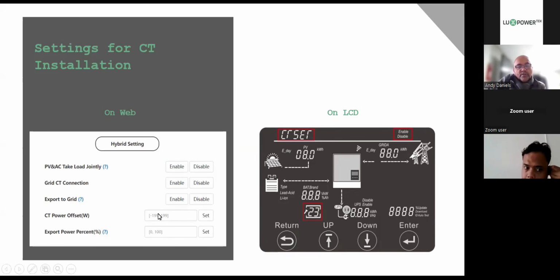So in other words, if your CT is pushing out power at maybe 50 watts, and you've set it at 0, then you can set a negative value here. You'll go negative 60 and set. It simply means that when you're generating PV power, it will always retain or pull in 60 watts from the grid to make sure that the CT doesn't export to the grid by mistake. Okay, and then if you're doing the settings on your LCD, you're going to go through up to setting number 23. You'll see here it says CT set, and you can enable or disable it here.